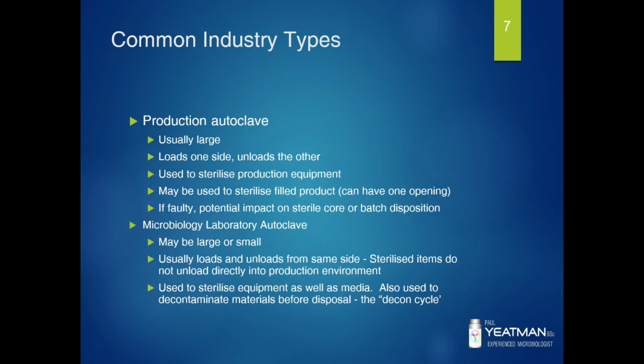It's important to note here that if the autoclave is faulty or hasn't been validated within a certain amount of time and those cycles post-validation are no good, there's a risk to the end user. For microbiology, the autoclave has multiple roles, so you could be using the autoclave to sterilise equipment into the sterile testing suite. You could be using it for media making, decontamination cycles, and for preparing equipment for environmental monitoring. So if you're using an autoclave to sterilise equipment into the sterile testing suite, you could have a front and a rear door. Alternatively, you could just have one door, and once the item's been sterilised, it could be put into an airlock or a pass-through for the testing suite. So it all depends on whatever procedures you have and how things are set up in the lab.